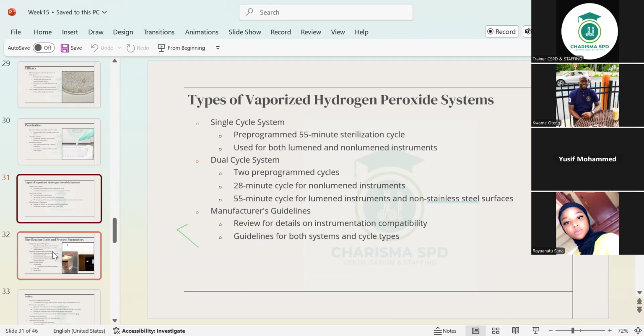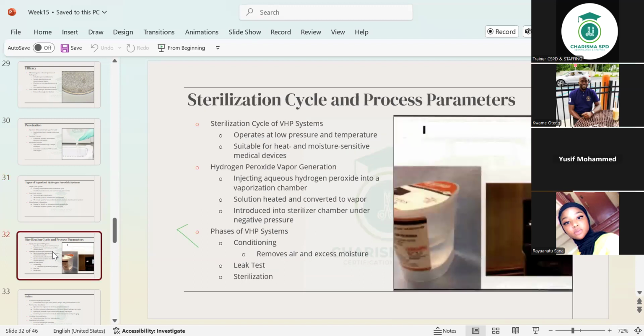But above all, you need your manufacturer's guidelines, the IFU. The cycle and process parameters are set already. Okay? But what you know is, I told you this one was around 131 degrees Fahrenheit. Compared to the steam, which is 270 degrees Fahrenheit, this one operates at low pressure and low temperature. The higher the pressure, the higher the temperature, right? The higher the temperature, the higher the pressure. This one is low pressure and low temperature. That's what I told you, around 131, which is low compared to the 270 that we use for steam.